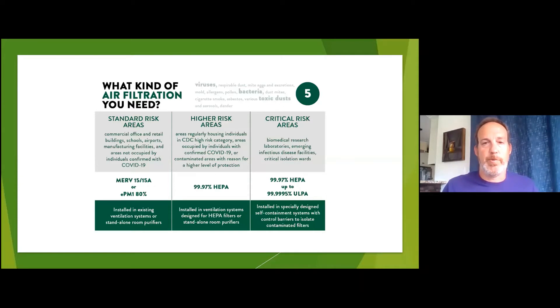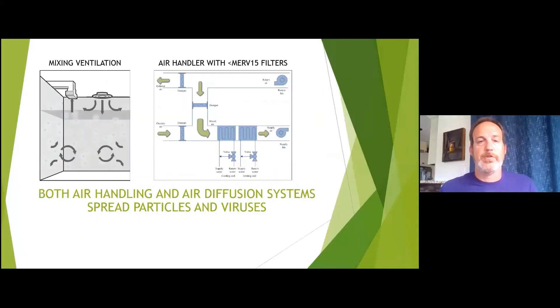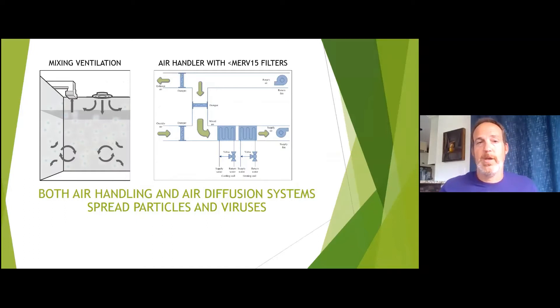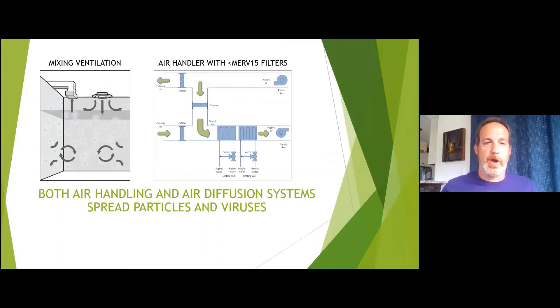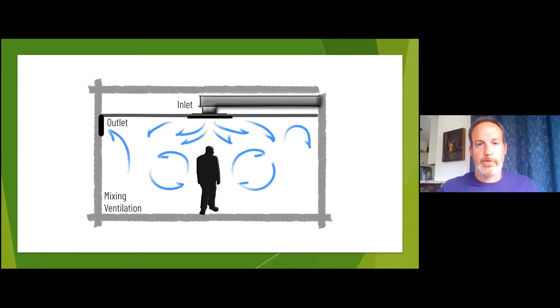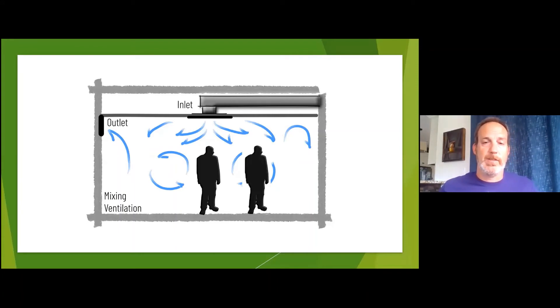But is that going to solve the problem? Not necessarily. There are two ways to propagate a virus by particle size around a building. One is with an air handler with an insufficient filtration system, but the other, which is common to almost all buildings, is a mixing ventilation system where we move the particles throughout the space for even distribution. If we have one person per space and we have sufficient filtration in the air handler, we're safe. But let's add a person with the virus and now we're mixing the air in the space and we are no longer safe regardless of the filtration in the air handler.